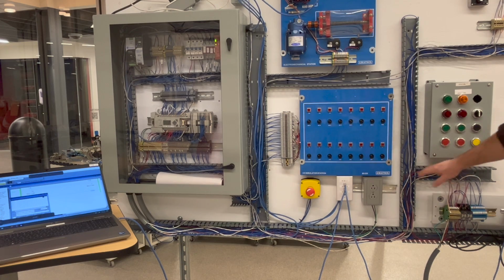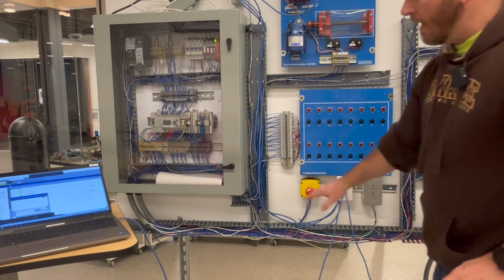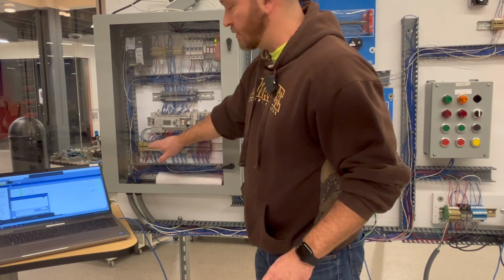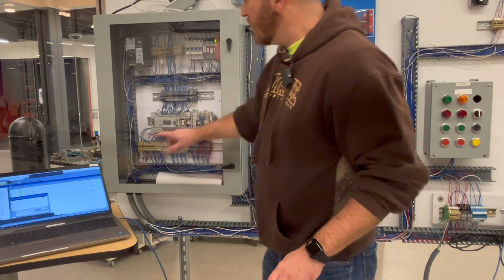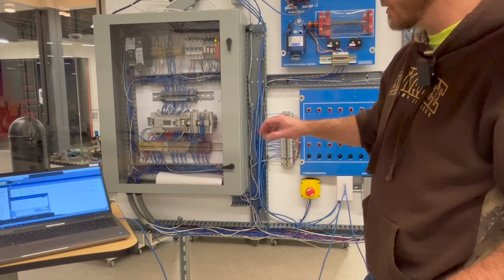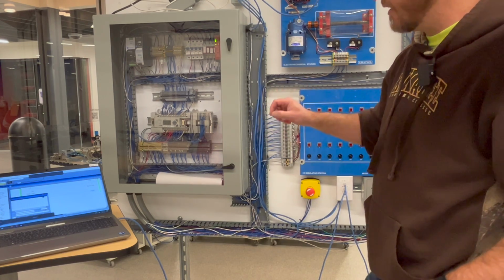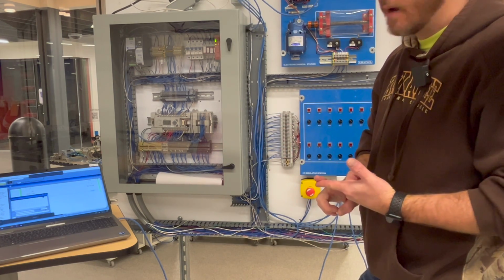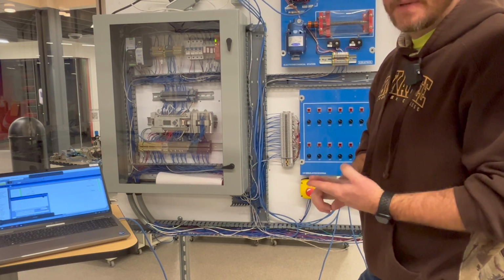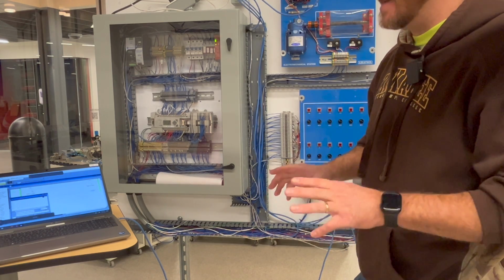So now, if I were to trace these wires back, I would find very quickly that there are no terminal blocks in here or up until the point where we actually get into the control panel itself. So let's go ahead and dive into the control panel and how we could figure out, is this a wiring problem now, or is the output on the PLC bad? So that's the next phase.